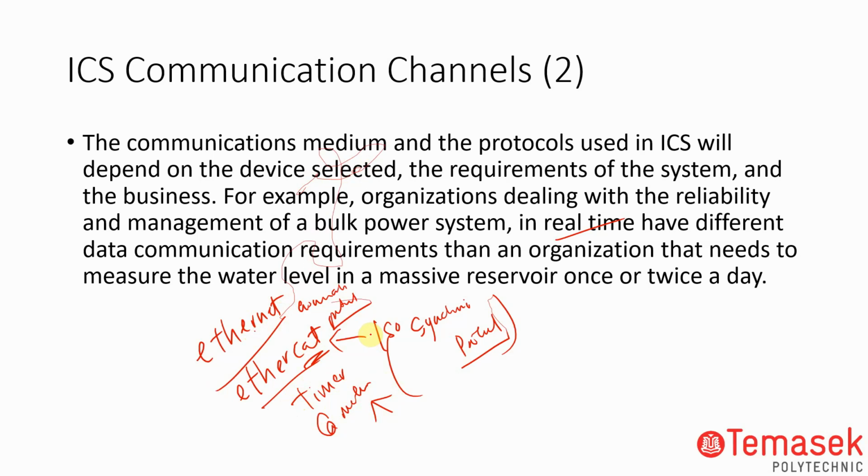Okay, which means that it's costly lah to do this for certain components. Ethernet on the other side is cheap because every card costs less than $35 each. This EtherCAT is easily more than $100 each per node. Okay, so there's the key differences. There is costing differences. It's possible to make Ethernet as good as EtherCAT by putting in a thing called a master clock. Okay, I don't know the actual price. It's easily more than $10,000.